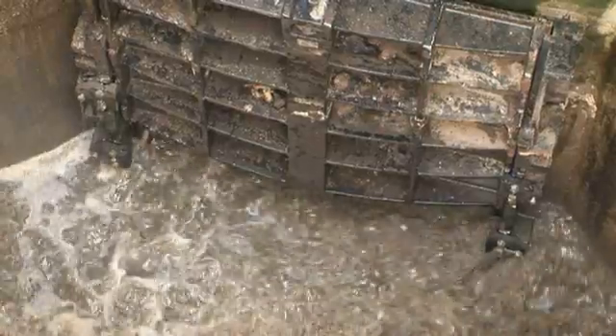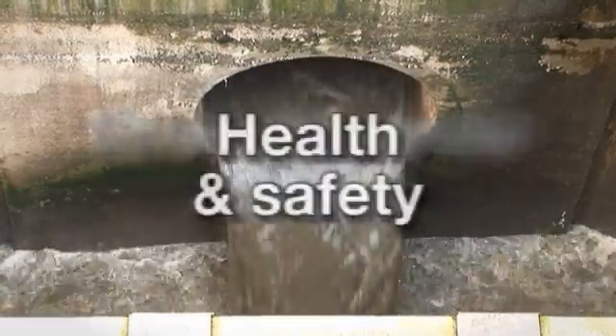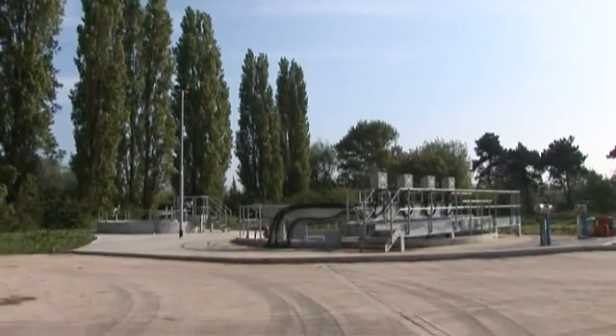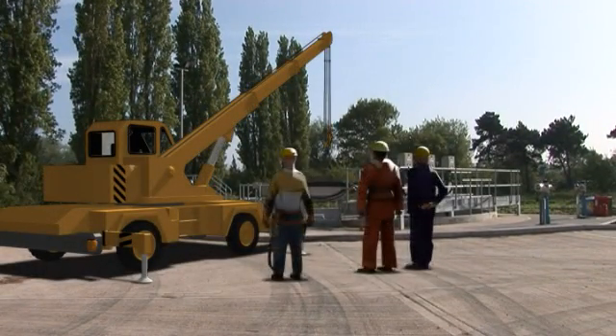A total system failure can result in effluent leakage with implications for the environment, human health, clean-up costs, and breaches of legislation. At the Worcester Works, pumps had to be removed from the well, split open, and the debris blocking it removed manually. As well as being a nasty, unpopular job, it was also expensive.